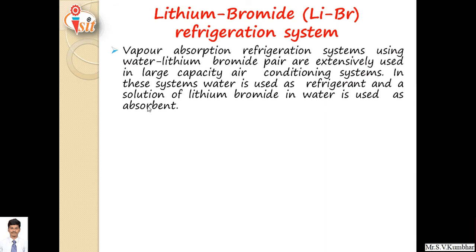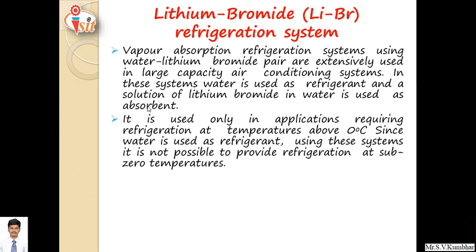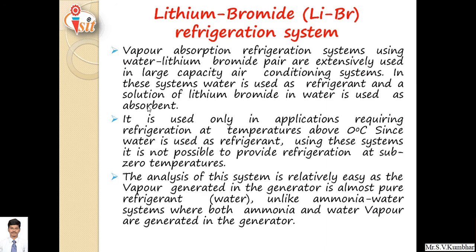Vapor absorption refrigeration systems using a water-lithium bromide pair are extensively used in large capacity air conditioning systems. In these systems, water is used as refrigerant and a solution of lithium bromide in water is used as absorbent. This system is used only in applications requiring refrigeration at temperatures above zero degrees centigrade, since water is used as refrigerant — it is not possible to provide refrigeration at sub-zero temperatures. The analysis of this system is relatively easy as the vapor generated in the generator is almost pure water, unlike the ammonia-water system where both ammonia and water vapors are generated.